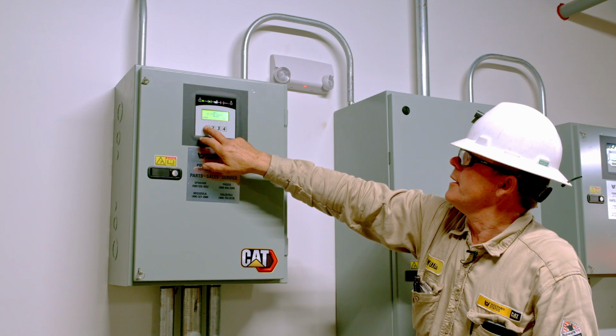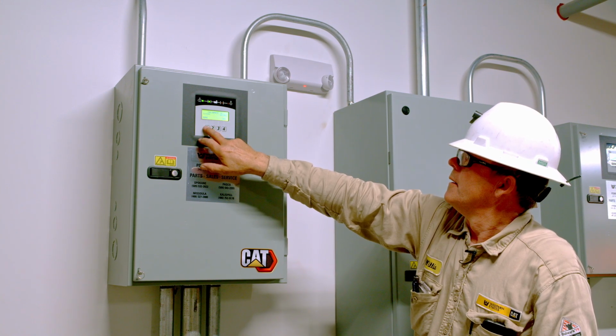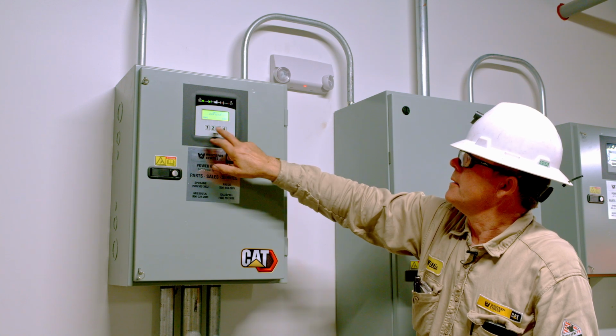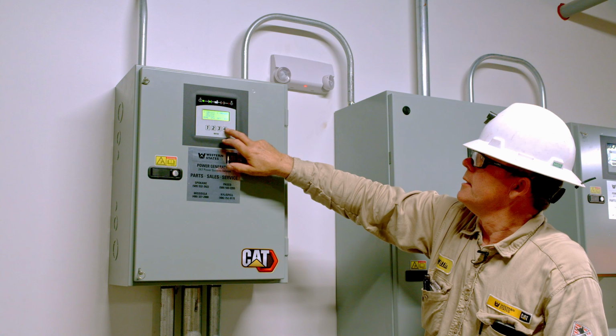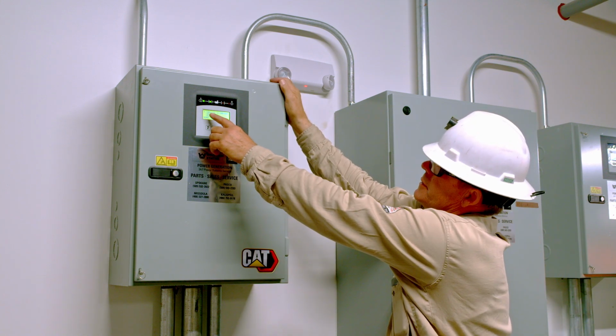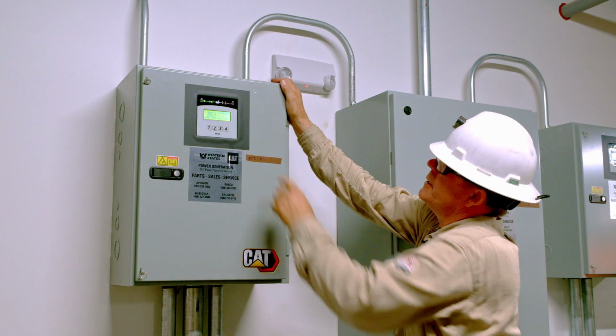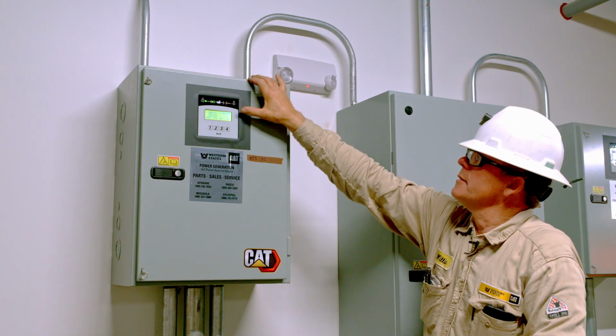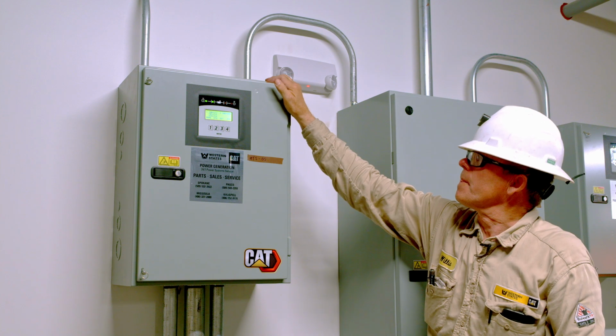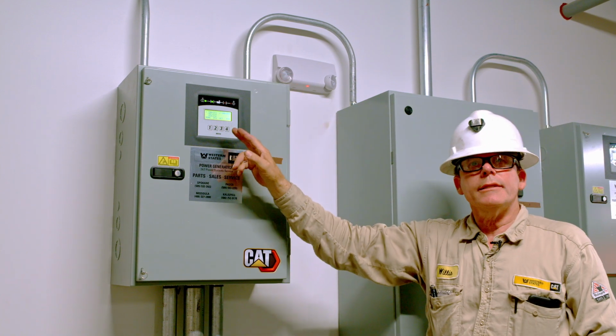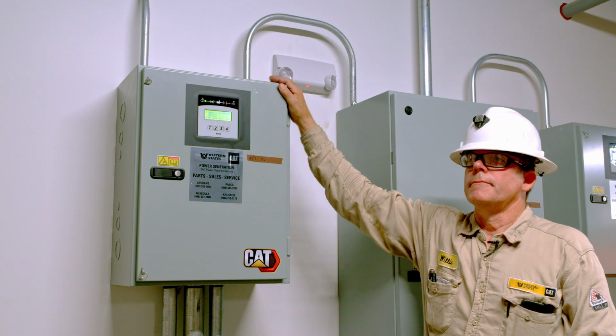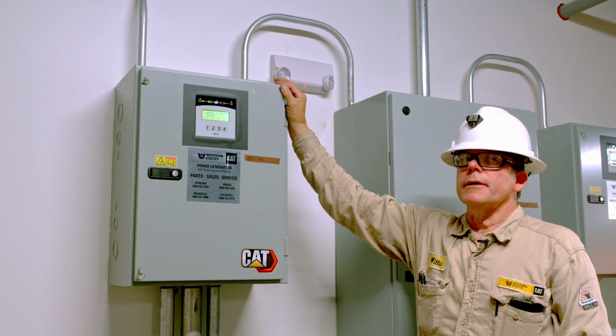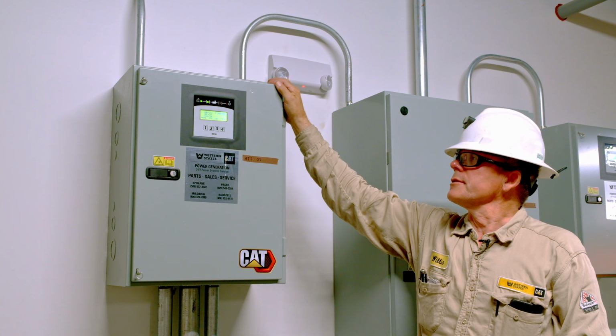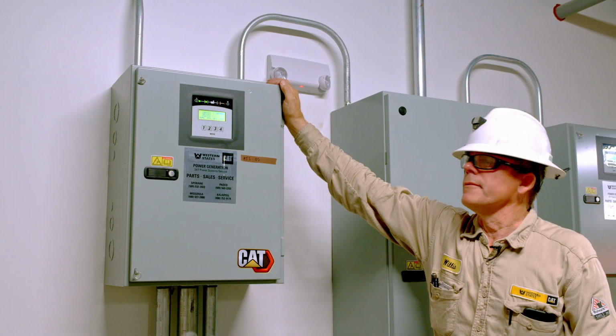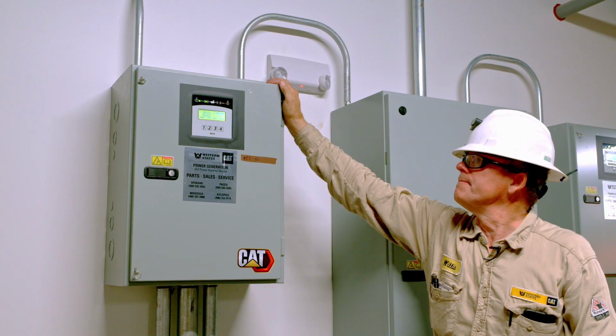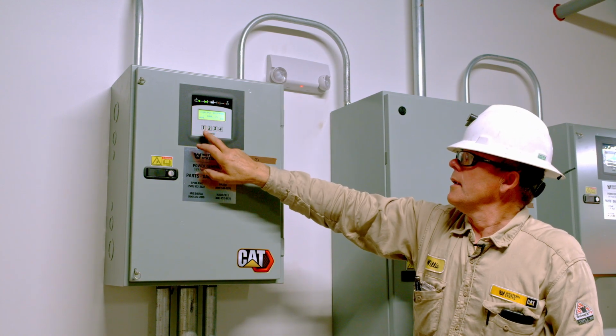And we've got a cool down delay of 5 minutes. And you can calibrate your voltage readings at that point. This menu here, you got voltage, all 3 phases on your utility, and it'll read A to B phase on generator. And if there's any timer that's active, it'll show in that screen. And you can't access the calibrate or the configure screen if it's running, or if you got an outage or anything. Any questions on the switch?